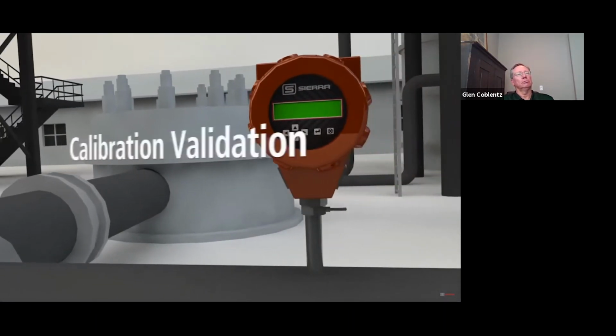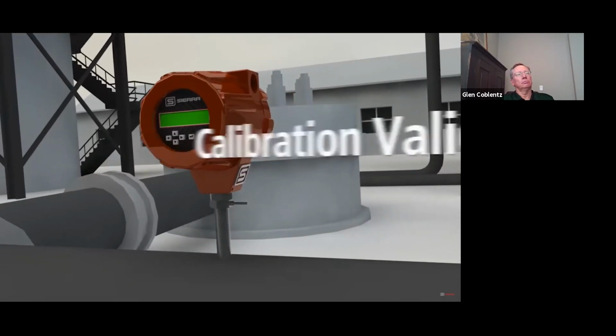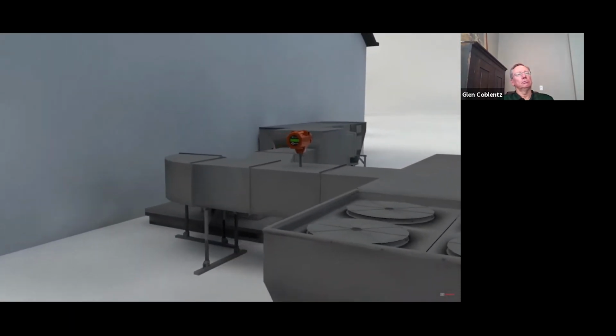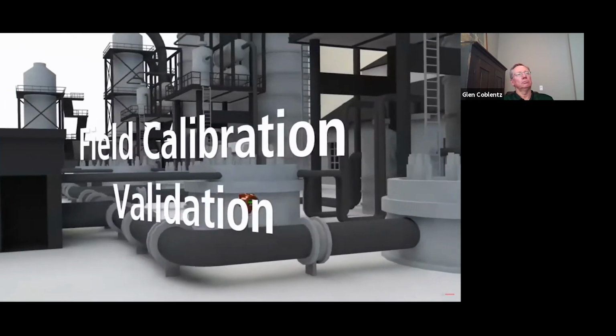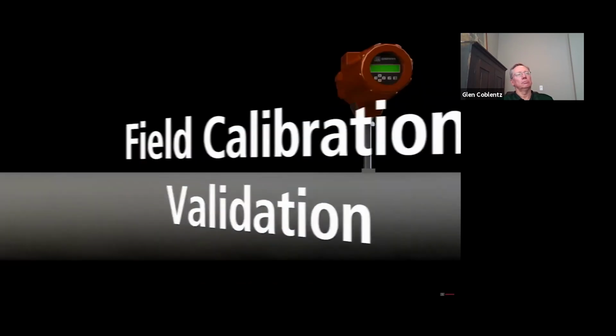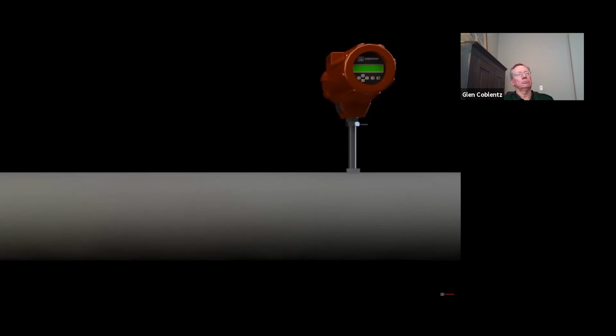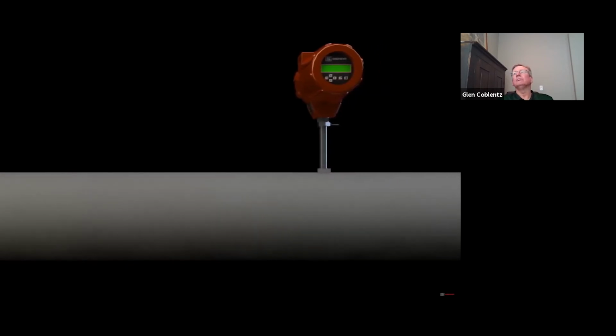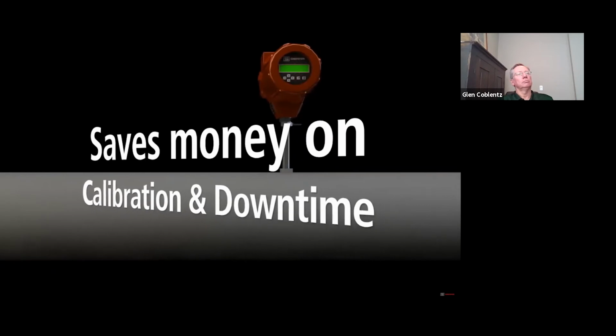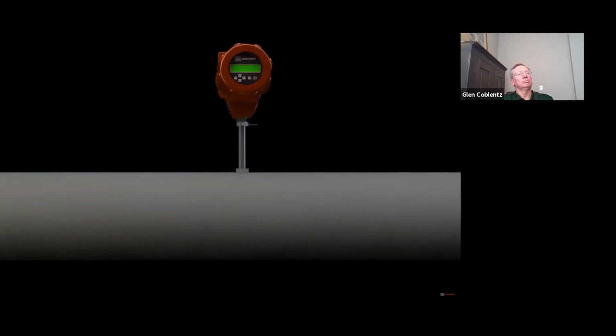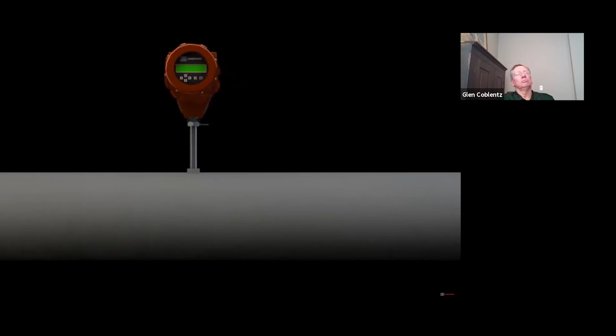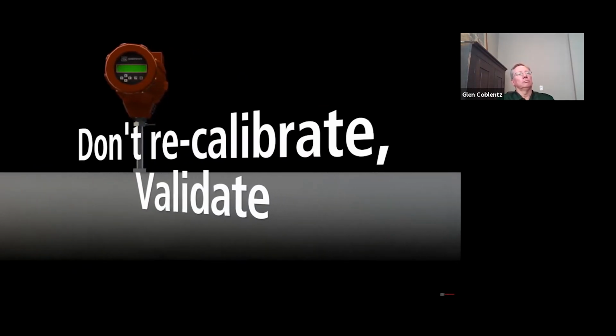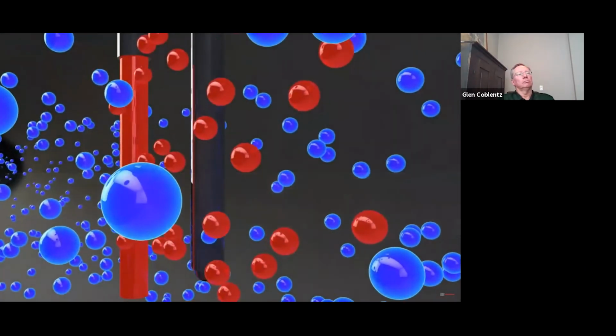Quality systems like ISO 9000 may require annual or even semi-annual calibration and validation of all measurement instruments in a facility. One of the nice features of thermal mass flow meters is that the calibration can be easily validated in the field at a very low cost. In situ or field calibration validation of thermal meters is a highly marketed feature because it saves money on calibration and downtime. Sierra customers have enjoyed this advantage for many years. Sierra's motto has always been, don't recalibrate, validate. But be careful, there is a lot more going on behind this statement than you may first think.